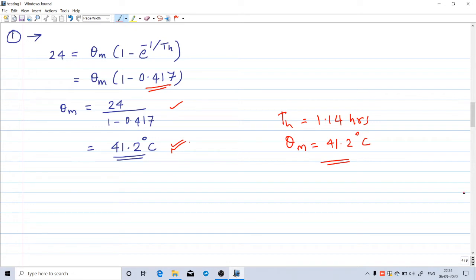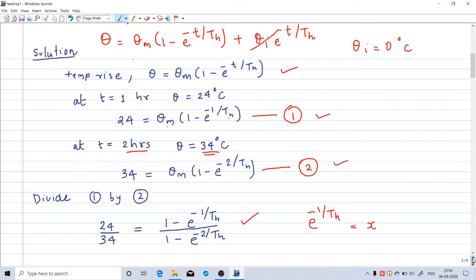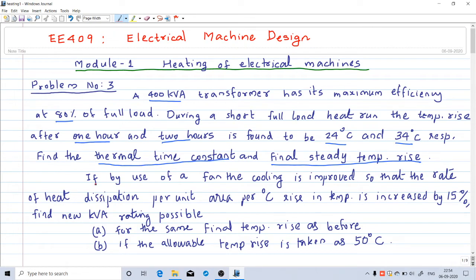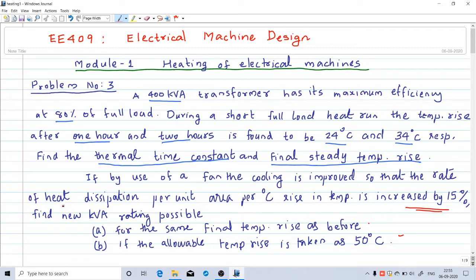The first part is complete. In the second part, if by use of a fan the cooling is improved so that the rate of heat dissipation per unit area per degree Celsius rise in temperature is increased by 15%, we need to find the new kVA rating for two cases: case A — the same final temperature rise as before (41.2°C), and case B — if the final temperature rise is 50 degrees Celsius.